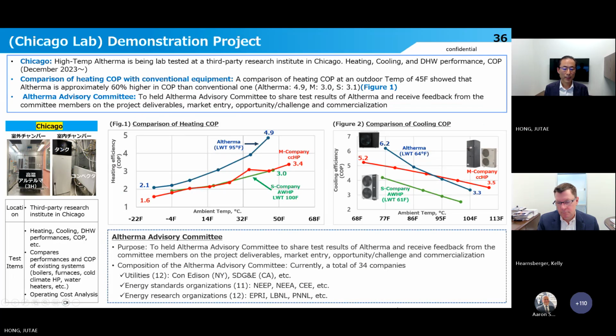Third, Chicago lab. High temperature Altherma is being lab tested at a third-party research institute in Chicago, with heating, cooling, and domestic hot water performance, COP, compared to those of boiler, furnace, and even cold climate heat pump. As you can see from figure 1, a comparison of heating COP at 45-degree ambient temperature shows that Altherma COP is 4.9, which is 63% higher in COP than cold climate heat pump.